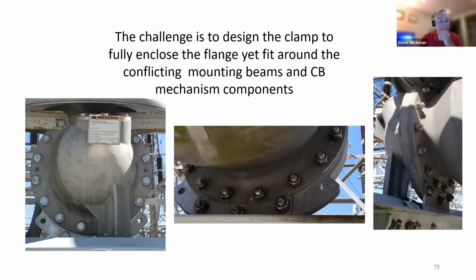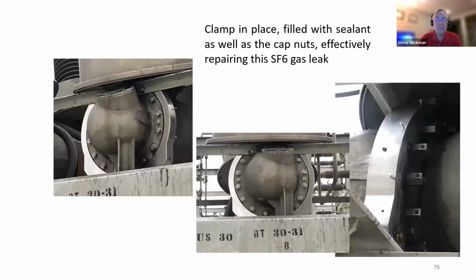And to add to the excitement, the middle phase pole is one way, and the two outboard poles, that configuration for that little ear there is offset by about 30 degrees. So each clamp would have to be different. The only one that was leaking was the center phase pole, B phase pole. So we fabricated a clamp to go around.